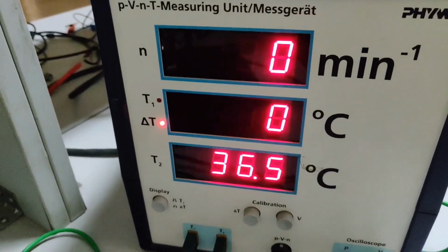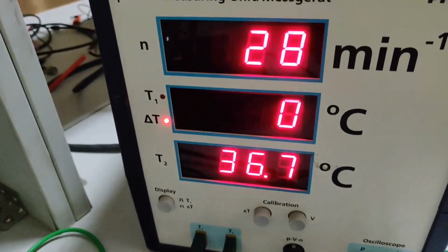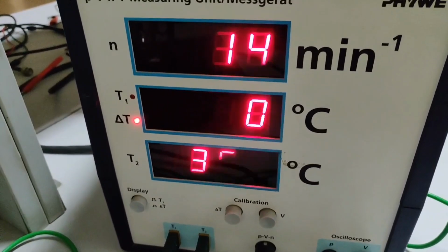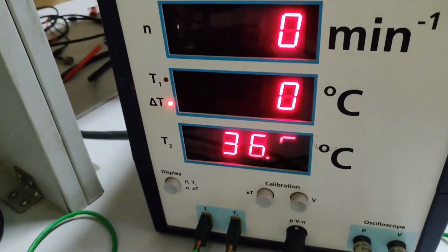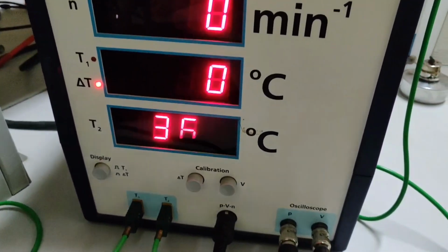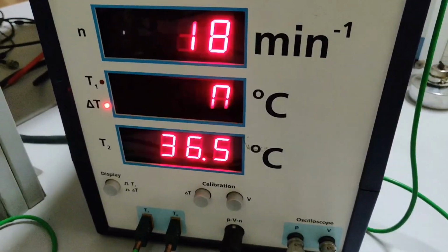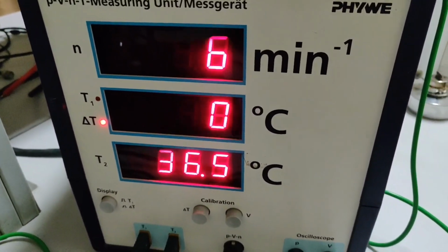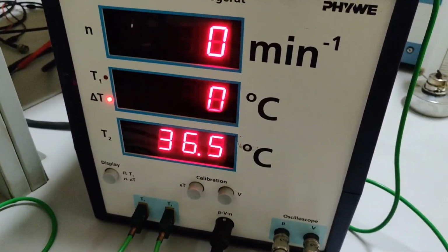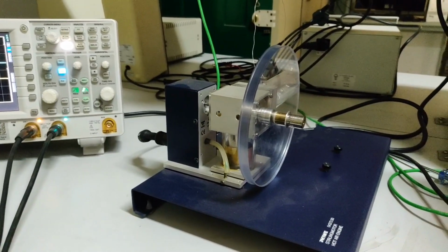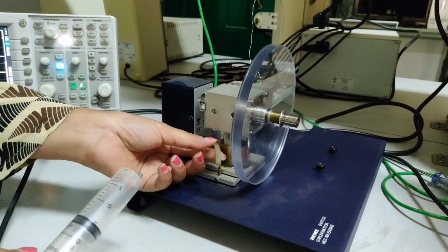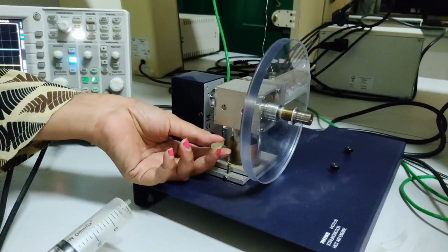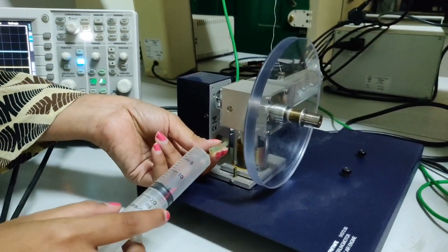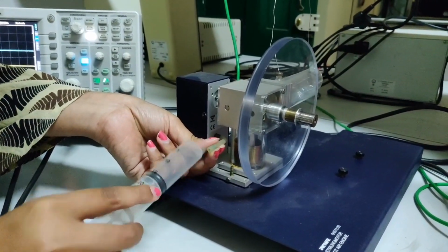So now once the temperature calibration is done, we also have to calibrate the pressure. Volume has already been calibrated by the manufacturer. The standard value is being given, so you will be using it in the calculation part. So now I will be showing you how the pressure calibration is done. For pressure calibration, we will be using this syringe. There is a small pipe given in this Stirling setup, into which I will be inserting this syringe.